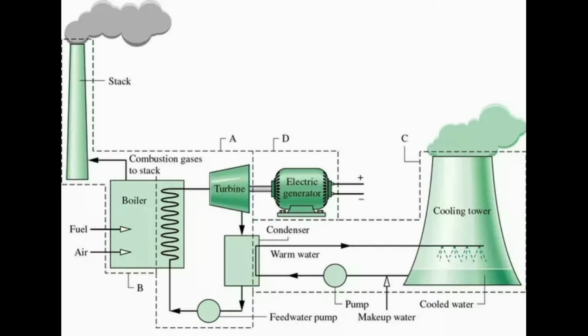and then it will go to the turbine. The turbine is shown here like this. It actually has three stages: HP turbine, IP turbine, and LP turbine. Steam at 560 degrees centigrade and 145 kg per centimeter square is admitted into the turbine. There, the energy in the steam will rotate the turbine blades. Then the rotor will rotate, and the turbine rotor and alternator rotor are the same. It is coupled in the middle, as shown.